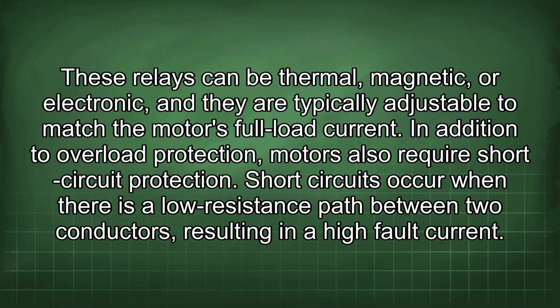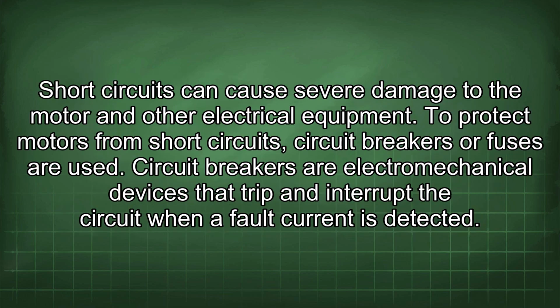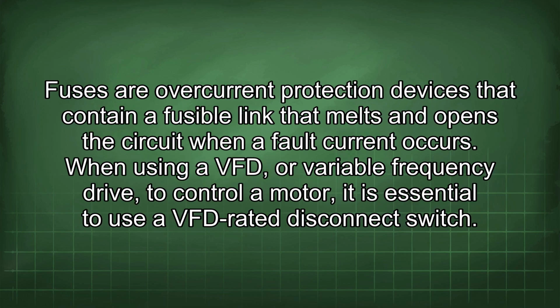In addition to overload protection, motors also require short circuit protection. Short circuits occur when there is a low resistance path between 2 conductors, resulting in a high fault current. Short circuits can cause severe damage to the motor and other electrical equipment. To protect motors from short circuits, circuit breakers or fuses are used. Circuit breakers are electromechanical devices that trip and interrupt the circuit when a fault current is detected. Fuses are overcurrent protection devices that contain a fusible link that melts and opens the circuit when a fault current occurs.